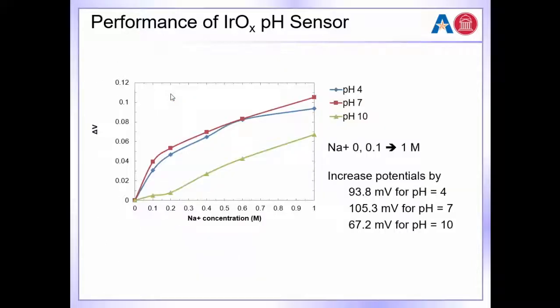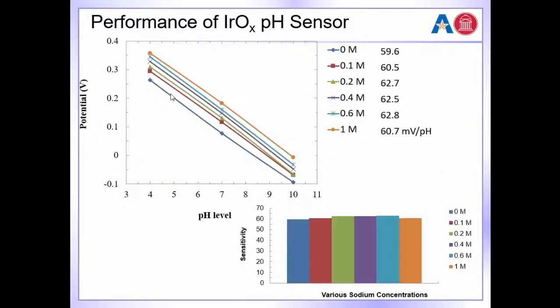And then we plot the potential drift by the concentration of the sodium, and you can see that they are a little bit different. For acid and neutral solutions, the drift is fairly matched, but in the alkaline solution, the drift is different. That's because in the alkaline solution, there are OH ions, which are negatively charged, and they interact with the sodium, which is positively charged, differently from the other two solutions. But it is obvious that the sodium will affect the pH output.